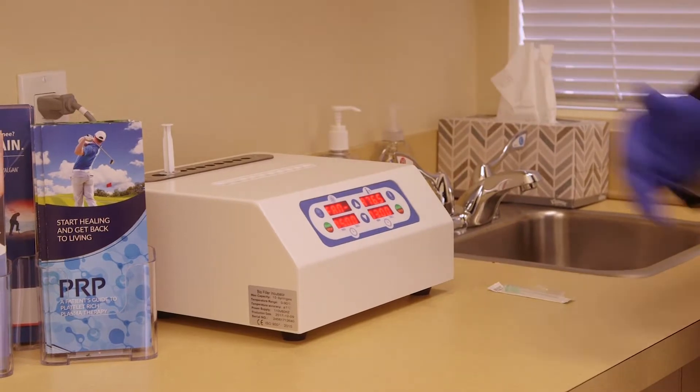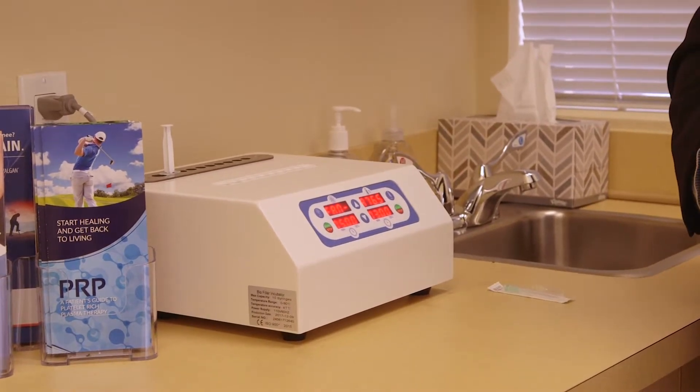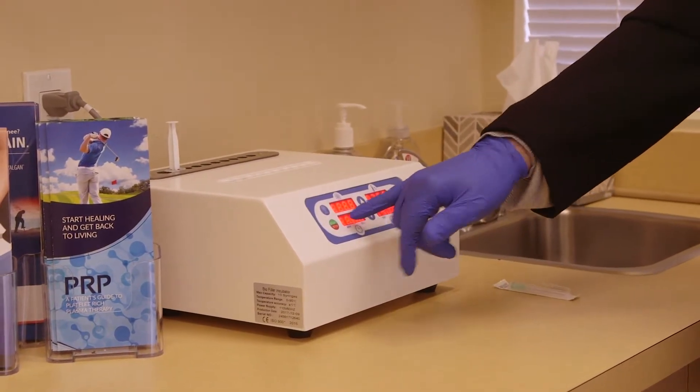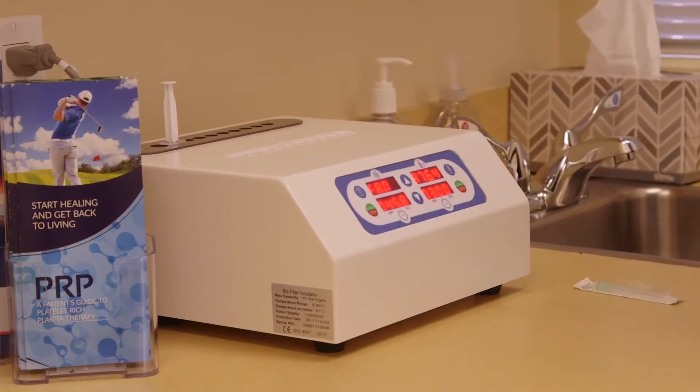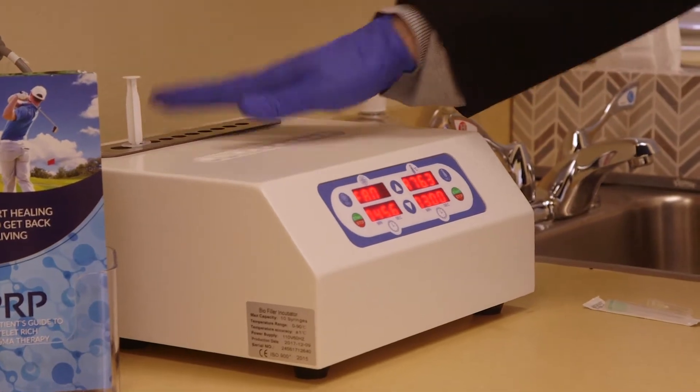Take the plasma and move it to the cooling section of the device. This will stop the thrombin cascade so the coagulation process will discontinue and the product won't get too thick. We have it set for five minutes of cooling time. Press start and it will cool this sample.